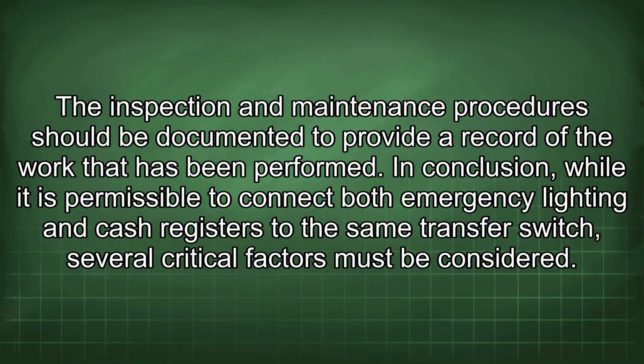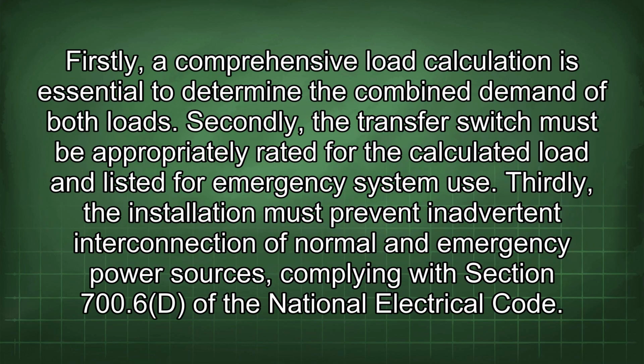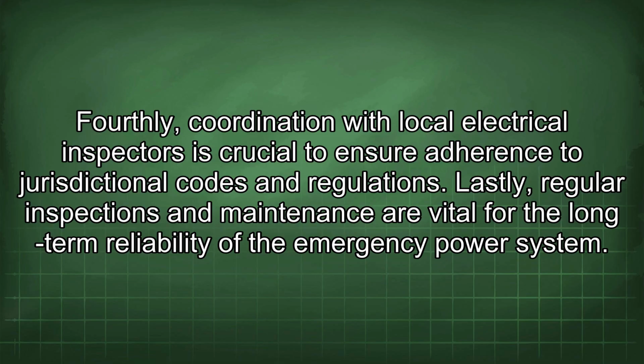critical factors must be considered. Firstly, a comprehensive load calculation is essential to determine the combined demand of both loads. Secondly, the transfer switch must be appropriately rated for the calculated load and listed for emergency system use. Thirdly, the installation must prevent inadvertent interconnection of normal and emergency power sources, complying with Section 700.6d of the National Electrical Code. Fourthly, coordination with local electrical inspectors is crucial to ensure adherence to jurisdictional codes and regulations.